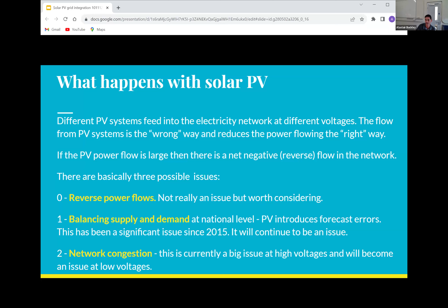So reverse power flows, and I've taken from Road Knight Taylor here, saying basically there's not an implicit issue in terms of the way transformers work. Transformers can convert from high voltage to low voltage and low voltage to high voltage. But certainly if the power rating of the transformer is exceeded, that's going to be a bad thing. And some of the control components might not work under reverse power flows. So only certain substations will be able to support high reverse power flows, and there might be some replacement work to do there.